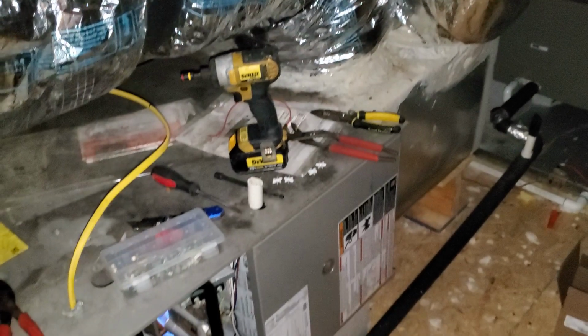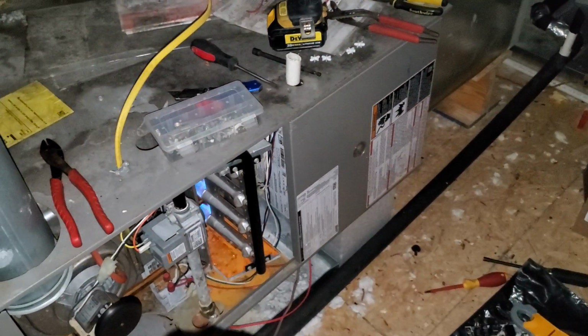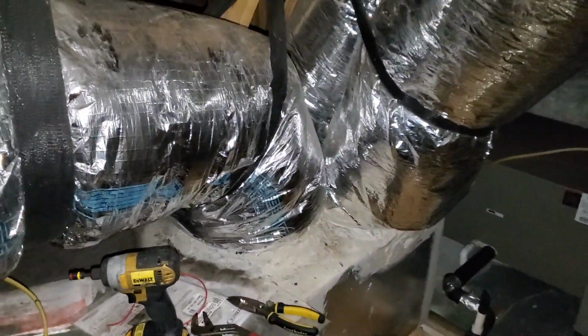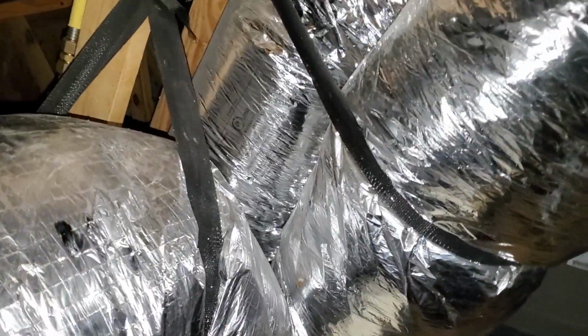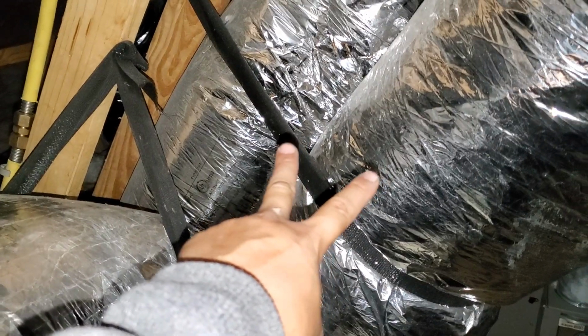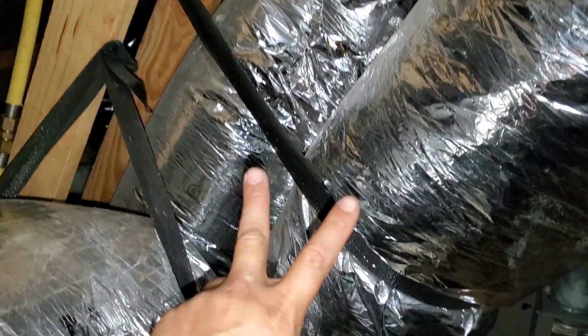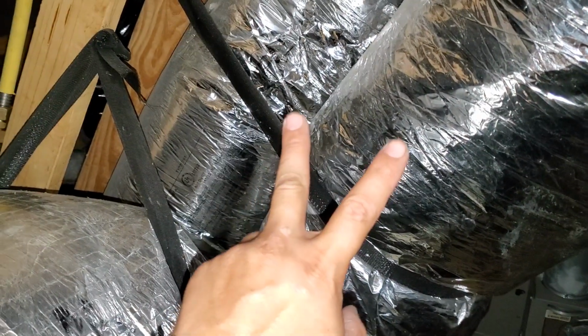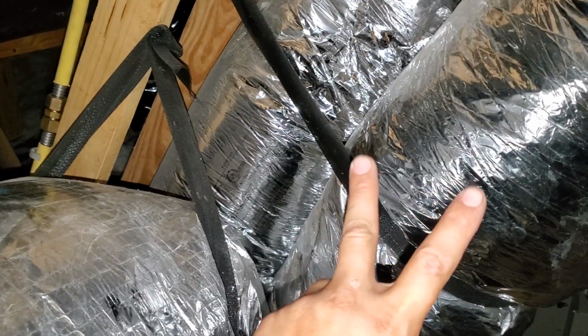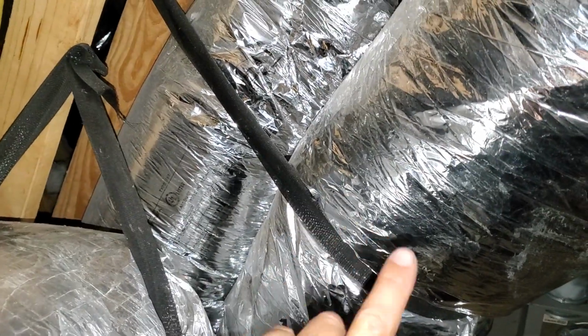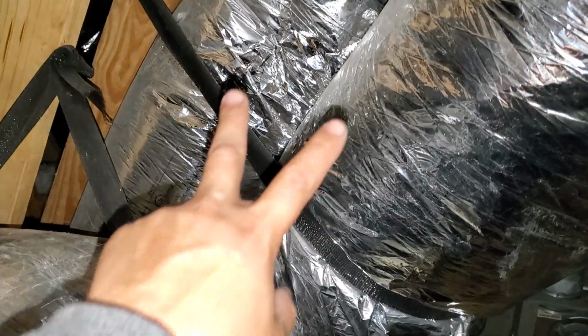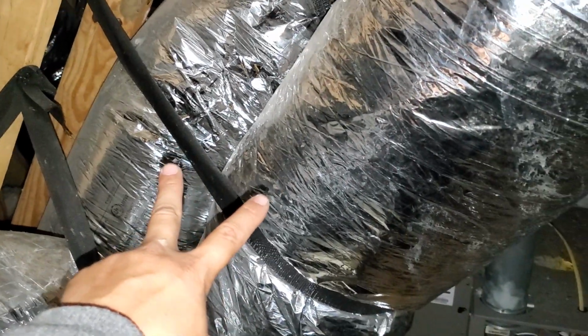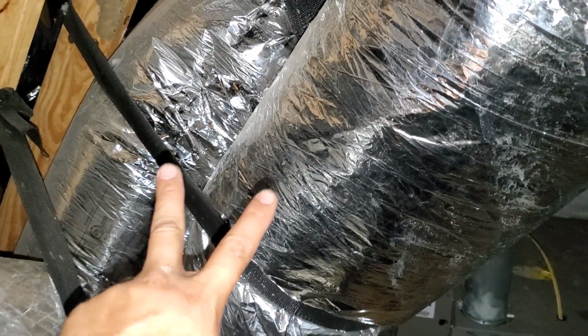So I started looking around. This is a 90,000 BTU furnace, and you can see we have another furnace over here. So I started looking at the ductwork and it instantly jumped out to me. These are our only two returns. 90,000 BTU furnace, 3.5 ton evaporator coil. I haven't seen the outdoor unit, so I'm guessing it's probably a 3, maybe a 3.5. But these two ducts are 10-inch. 10. So you've got a 12 bypass, two 10s, and that's it on this unit.